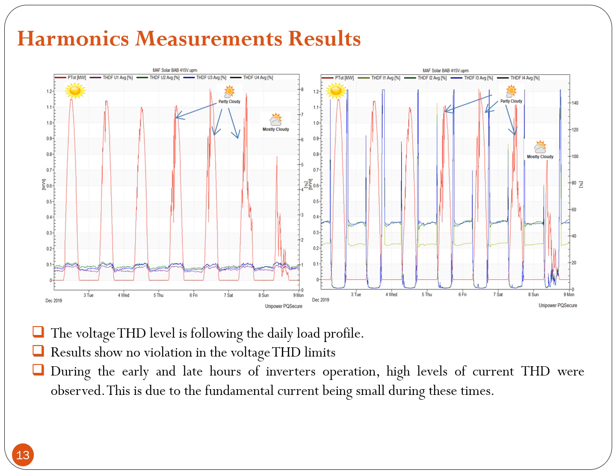Harmonic measurement results conclude that the voltage total harmonic distortion level follows the daily load profile. The result shows no violation in the voltage total harmonic distortion limit during the early and late hours of the inverter operation. High levels of current total harmonic distortion were observed. This is due to the fundamental current being small during this time.